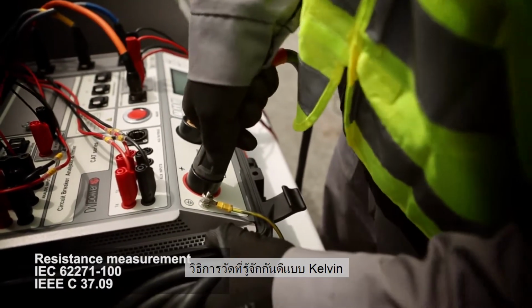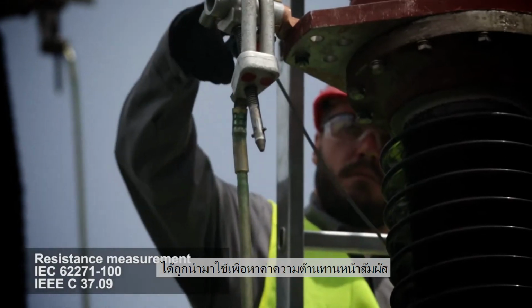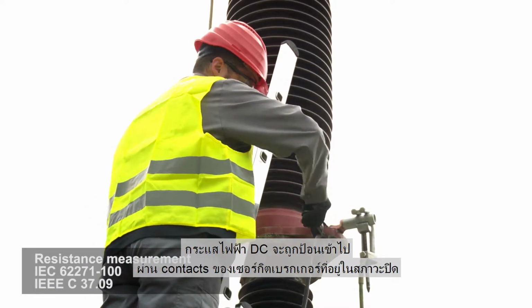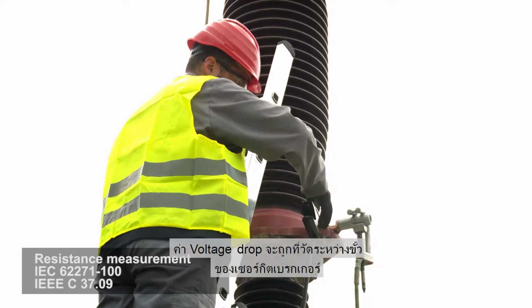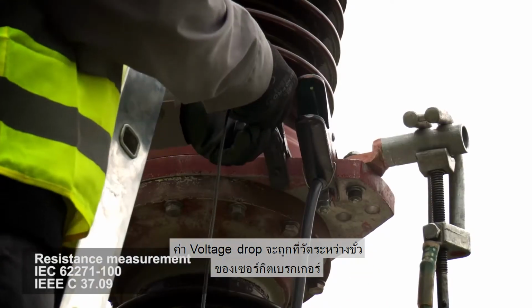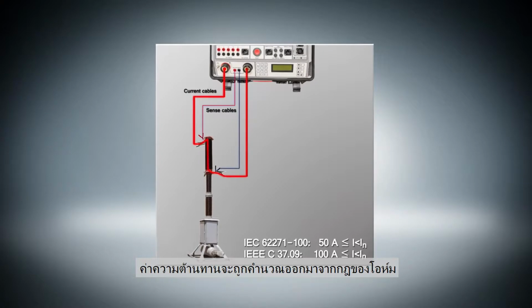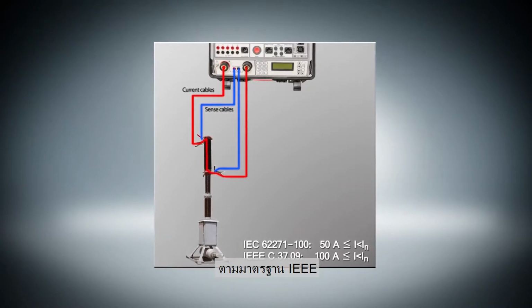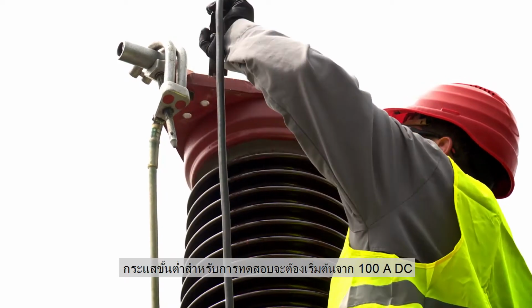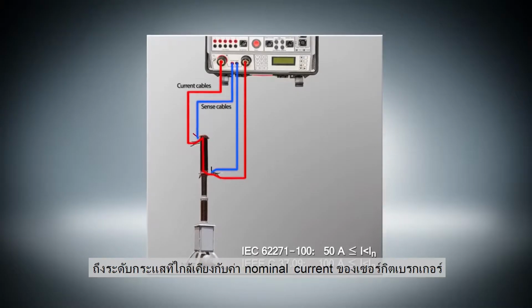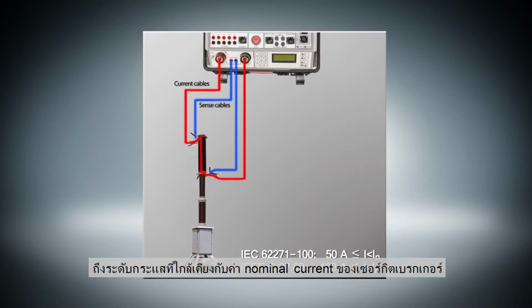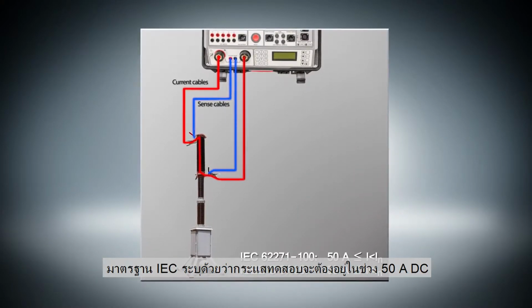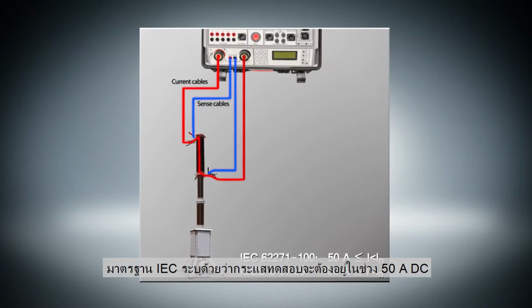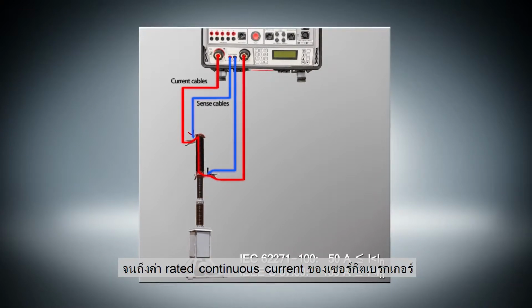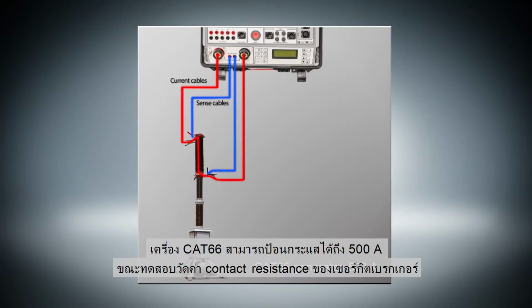The well-known Kelvin 4-point method is used for resistance measurement. DC current is generated through the closed circuit breaker contacts. The voltage drop is measured between the terminals of the circuit breaker. The resistance is calculated using Ohm's law. According to the IEEE standard, the minimum test current is from 100 amps DC up to as close as possible to a breaker's nominal current. The IEC standard defines the test current in the range from 50 amps DC to the rated circuit breaker continuous currents. CAT 66 can generate 500 amps during a contact resistance measurement test.